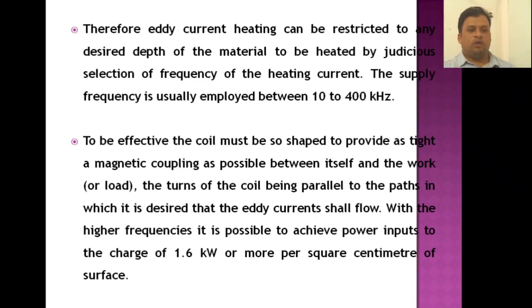The turns of the coil are parallel to the paths in which it is desired that eddy current shall flow. With high frequencies it is possible to achieve power inputs to the charge of 1.6 kilowatts or more per square centimeter of surface.